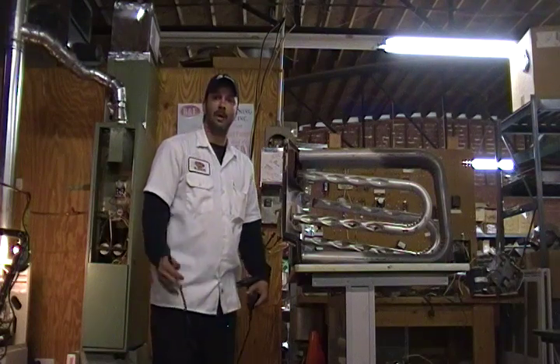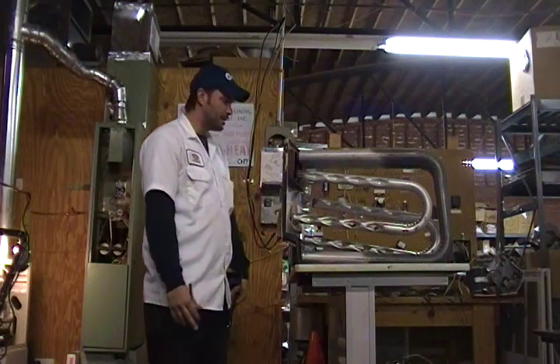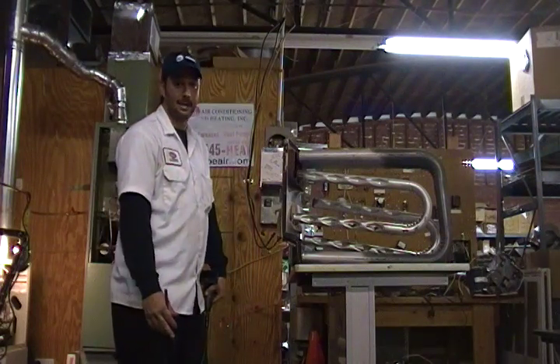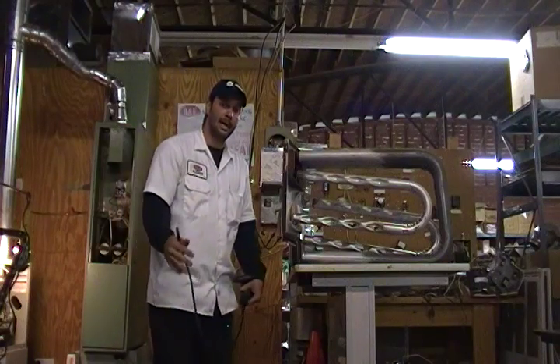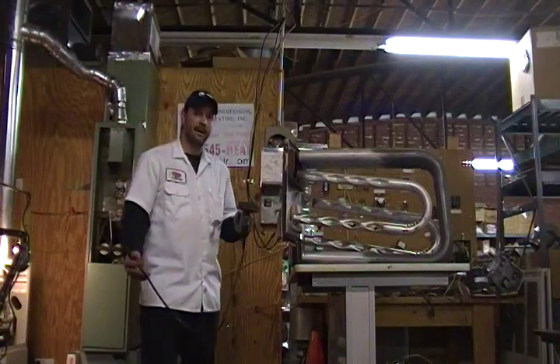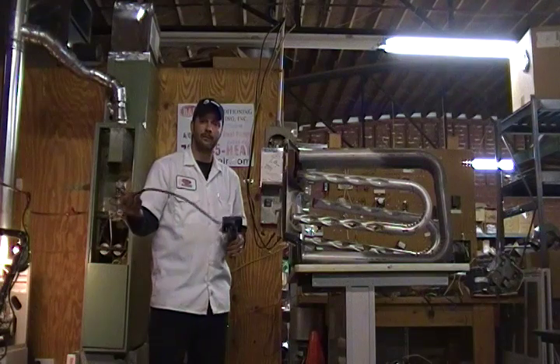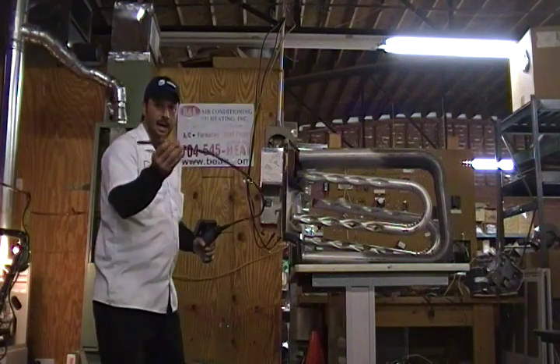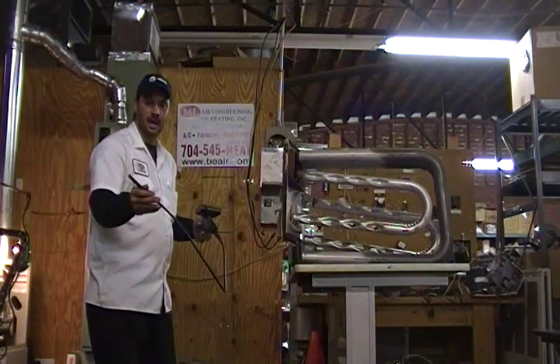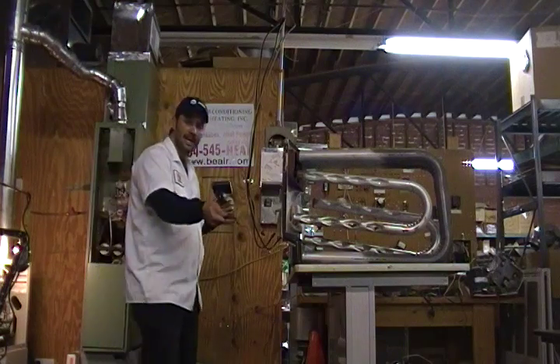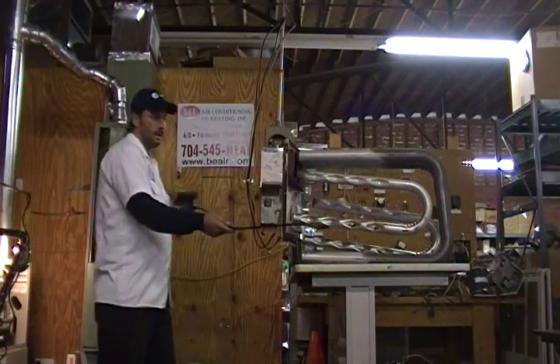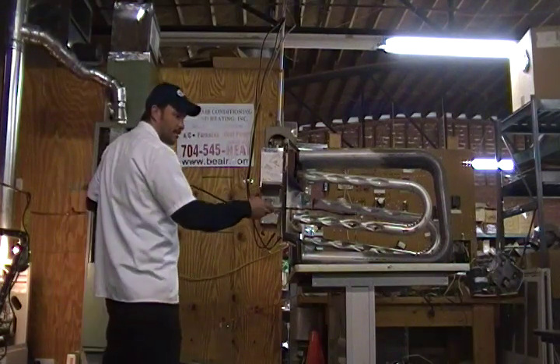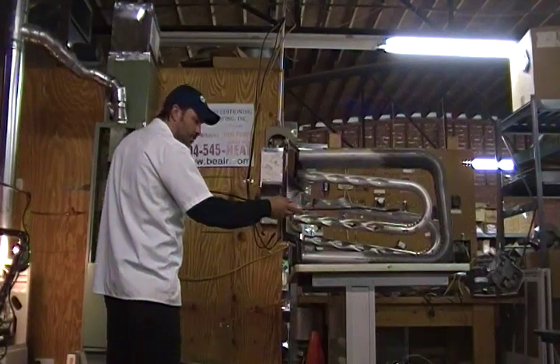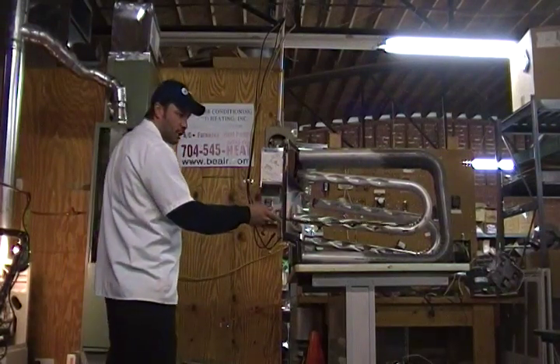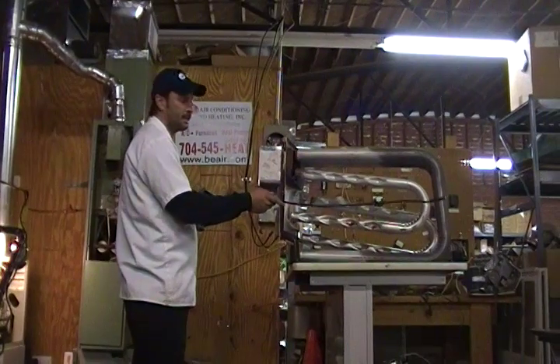I want to show you one of the many ways that you can inspect the heat exchanger to find out if it is in fact cracked, flawed, or letting carbon monoxide out. One of the current tools on the market right now is called a Seeker 400. It's a camera with a knob that lets you adjust the light, and it's got a long probe with the camera and light at the end. You can run it up inside the heat exchanger tubes and find out if there are cracks, weak spots, or rust.